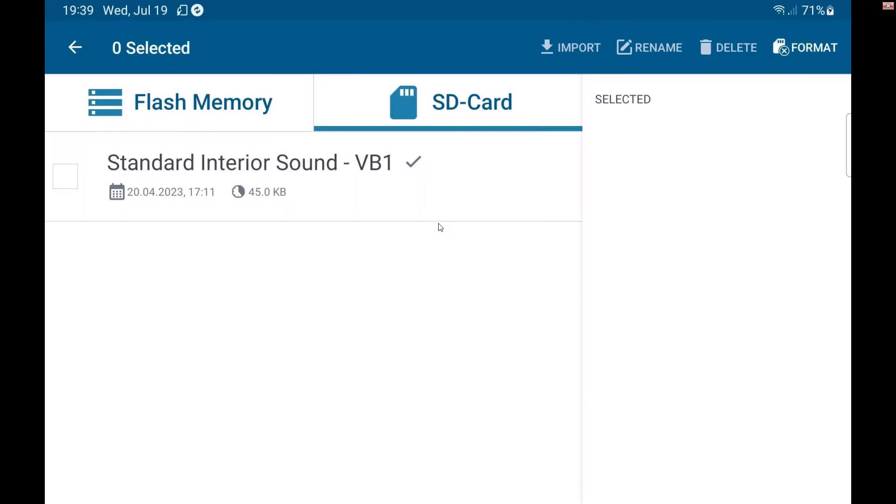Now, none of the data that I collect using the scope app is saved to the tablet at all. The raw data is saved to this micro SD card that is within the unit itself. And I can bring that micro SD card out, put it in the PC for more advanced processing and test lab at any time.